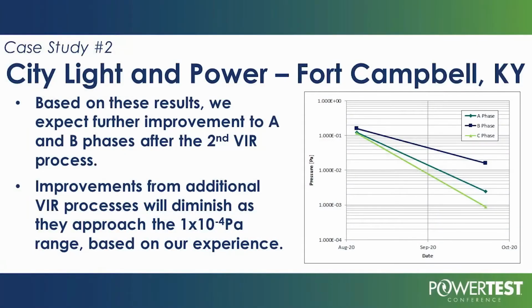Based on these results, we expect further improvement on A and B phase. There again, we see one phase where the effect is different. That means that the gases inside, or the manufacturing process on that interrupter, was not as solid. There'll be situations, there'll be outliers, but we basically can guarantee the 1 order of improvement. We can't guarantee the 2 orders of improvement that we saw on some of the interrupters on this job.